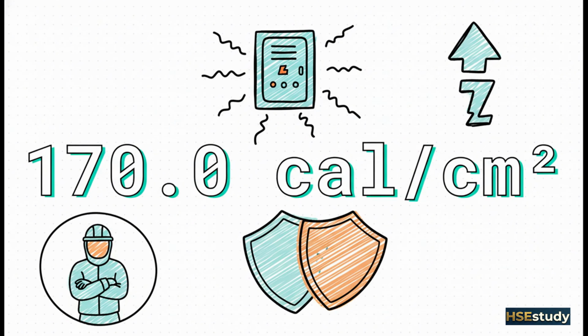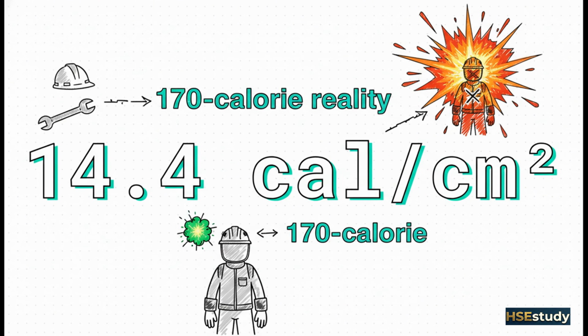This isn't just a theory, this is reality. We have documented case studies where, based on the breaker's actual time current curve, the clearing time was nearly 24 seconds. The true incident energy? 170 calories per centimeter squared. There is no PPE on the market that will save you from a 170-calorie event. It is simply unsurvivable. But if an engineer incorrectly applied that 2-second rule, the label on that same piece of equipment would read 14.4 calories.